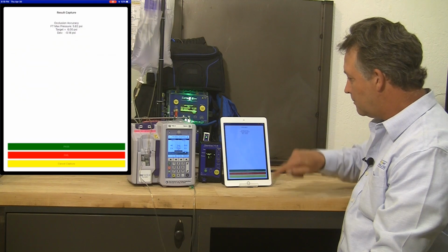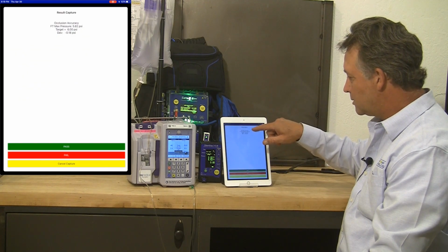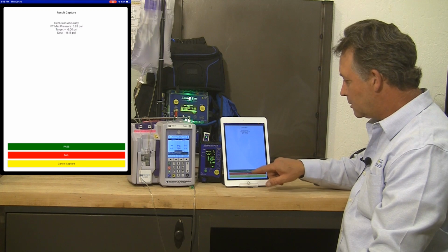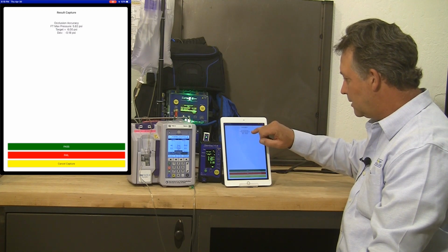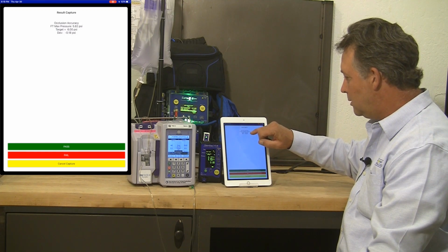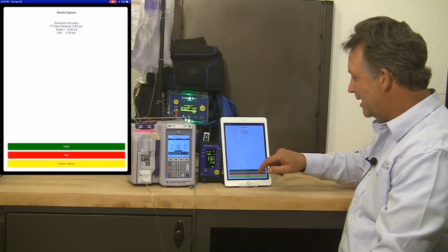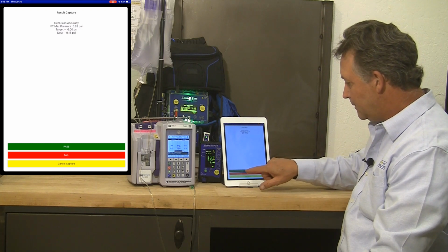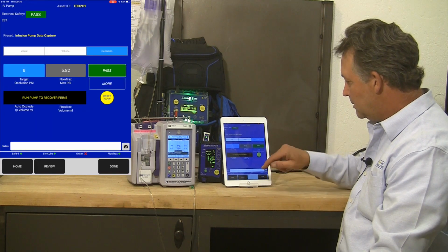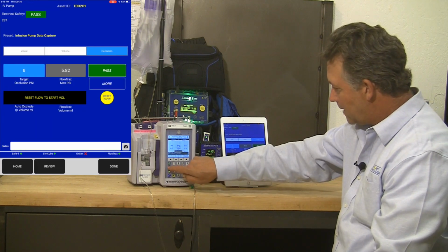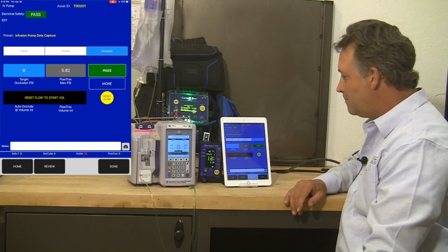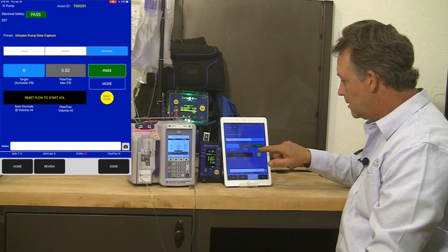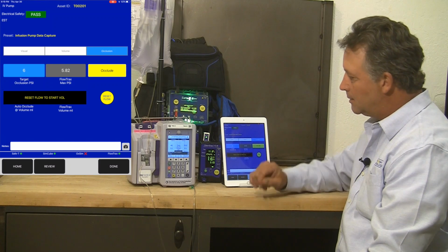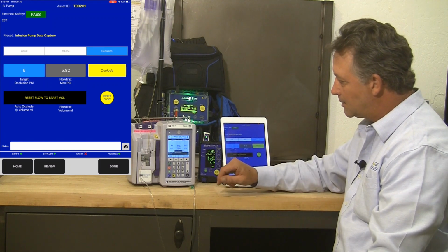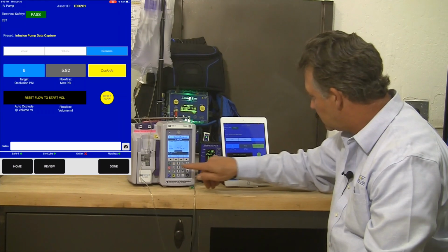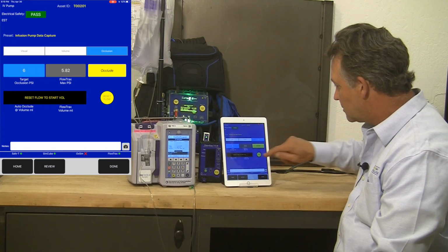I hit the capture button and I've actually got my results right there on the screen to make the determination of pass-fail. It's telling me that the max pressure was 5.82, target was 6, deviation was negative 0.18 psi. That's clearly a pass. Now, we want to stop the pump, program it for 10 psi, and hit the more button so that we can capture that second occlusion test at 10 psi. We're going to want to reset the FlowTrax before we restart.